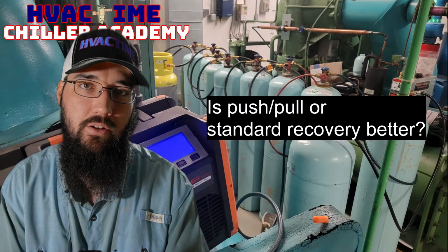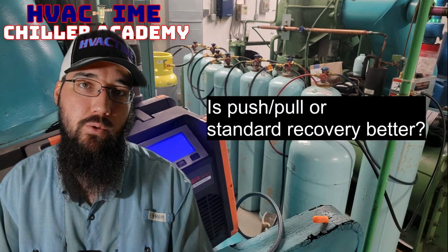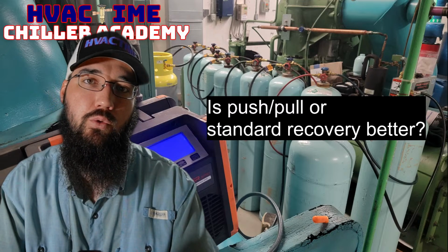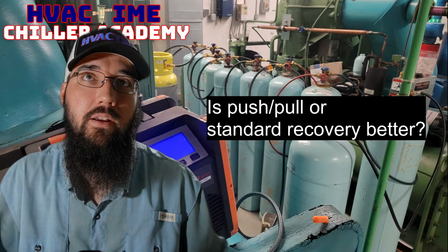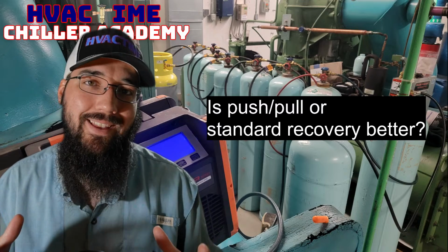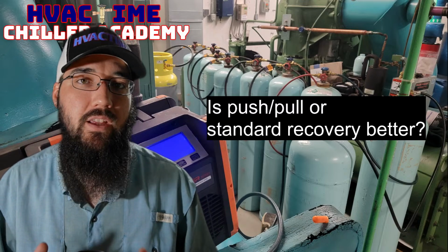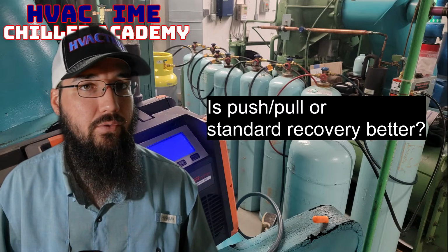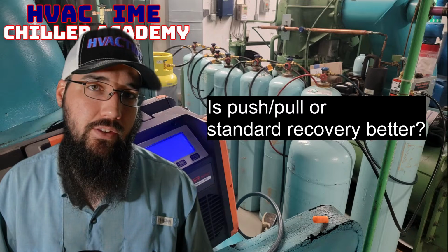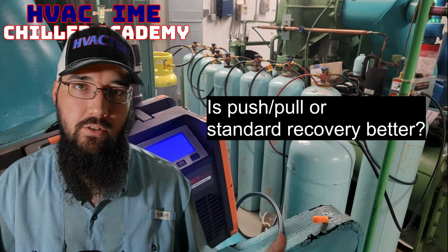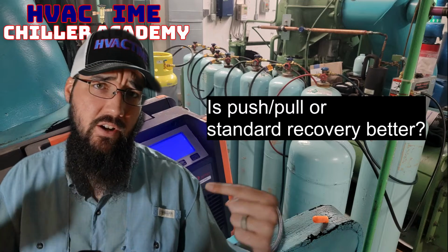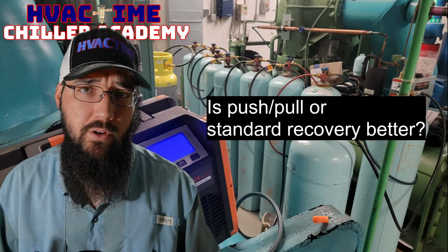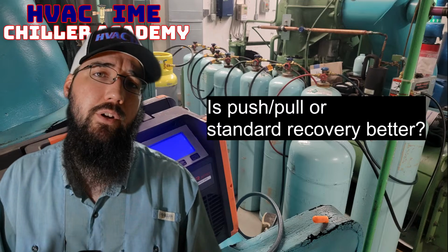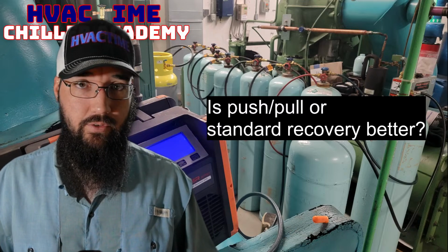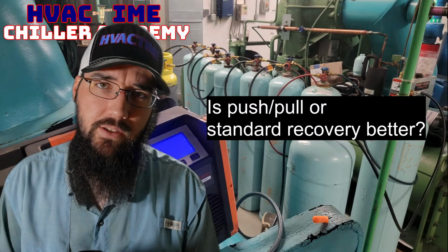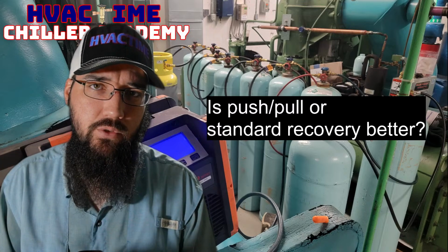That consolidated access is what makes push-pull so valuable - the ability to quickly move a large volume of liquid refrigerant, because liquid is what kills your transfer times, not vapor. Vapor doesn't take that long if that's all that's there. But when you've got pockets of liquid scattered throughout the machine and you have to boil all that liquid off to do the recovery - which is what a standard recovery ends up being - it takes forever. So if it's an option, push-pull will save you time.